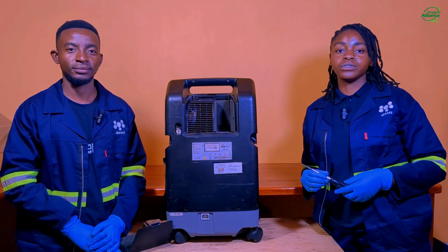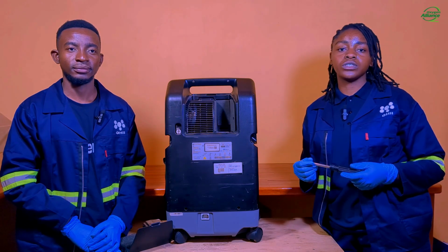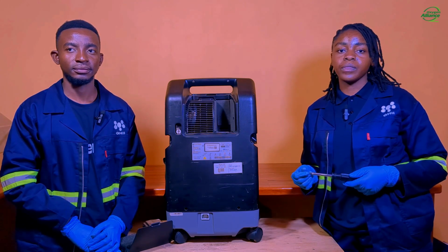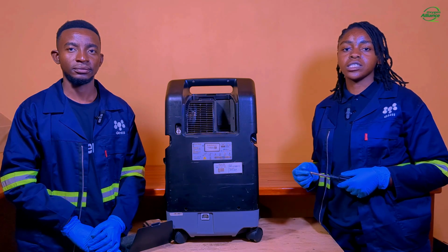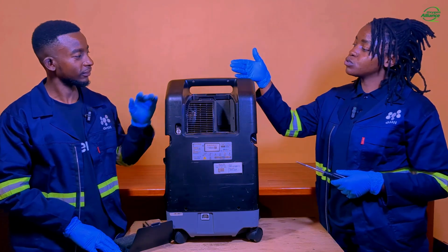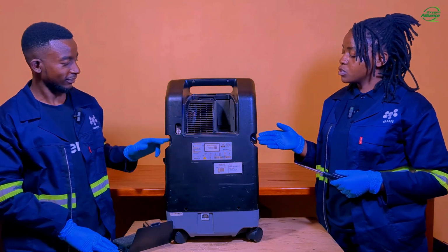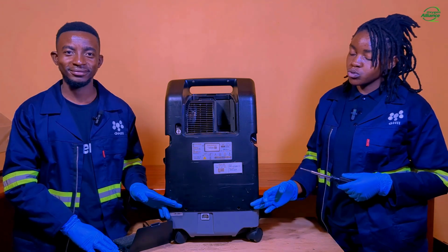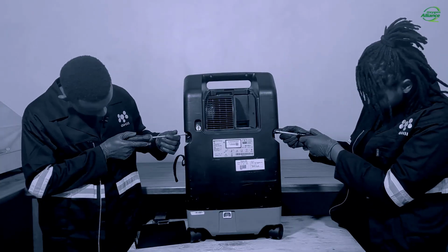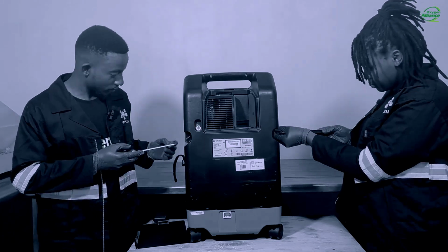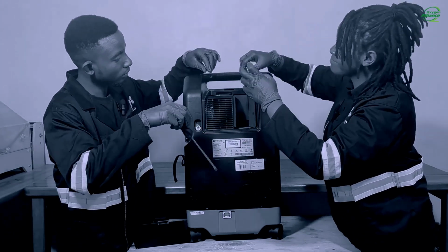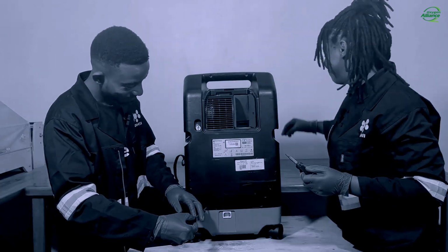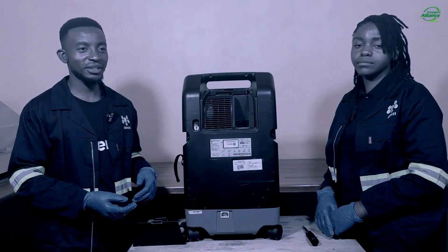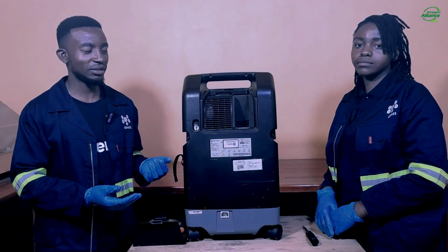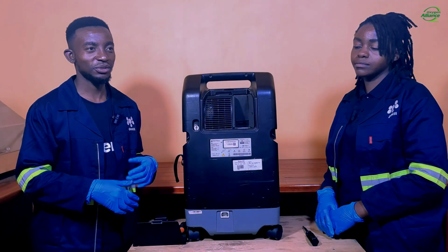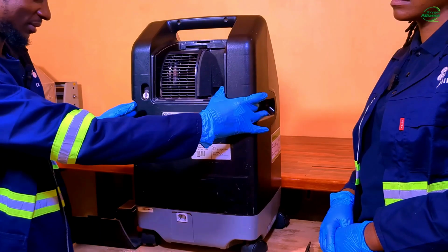So to open the back of the concentrator, you're going to use a Torx T25 or a flat screwdriver. And for this back cover, it has got 6 screws. So you have 2 screws at the top of the concentrator, 2 screws on the side, and 2 screws at the bottom of the back cover. Having unscrewed all the screws, now you can remove the back cover. So you can simply slide it out.